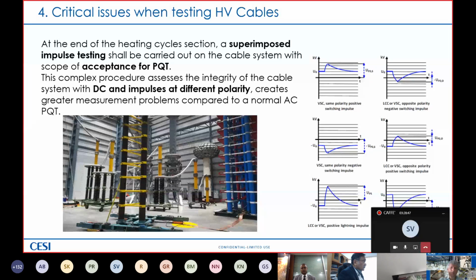As you can imagine, and you can also see from the diagram on the right side, you can reach about 2000 kilovolts, sometimes plus or minus. Other voltages can be reduced in case we have different polarity and so on. But for sure, this is a complication compared to only 10 positive, 10 negative lightning impulses or switching impulses to be performed after the HVAC test. These pictures are taken inside the laboratory in Mannheim, Germany, during one superimposed impulse test of a 525 kV cable system.